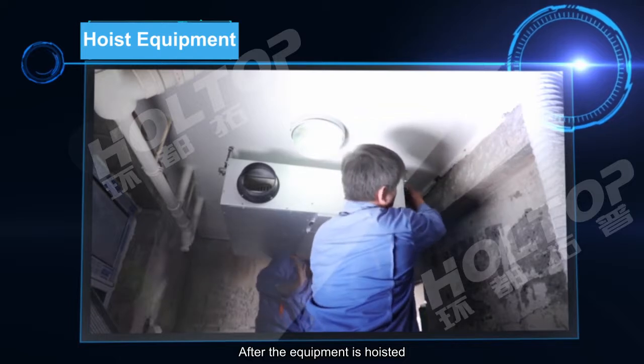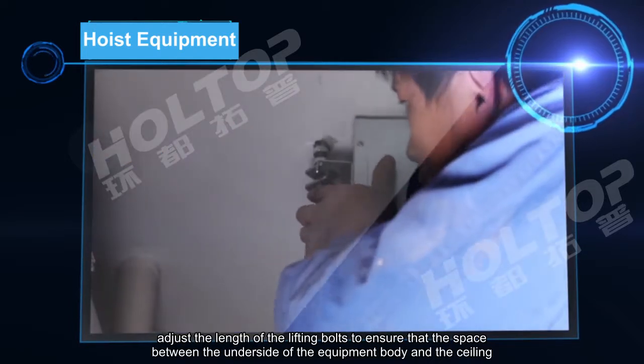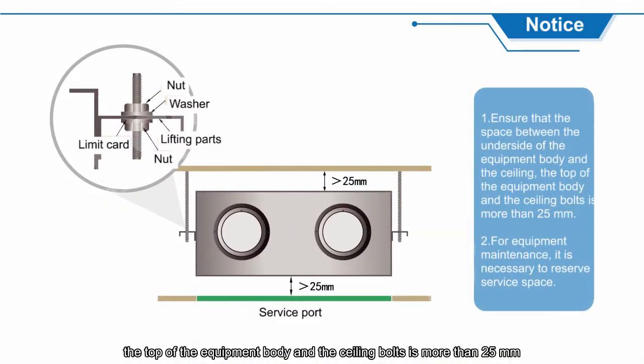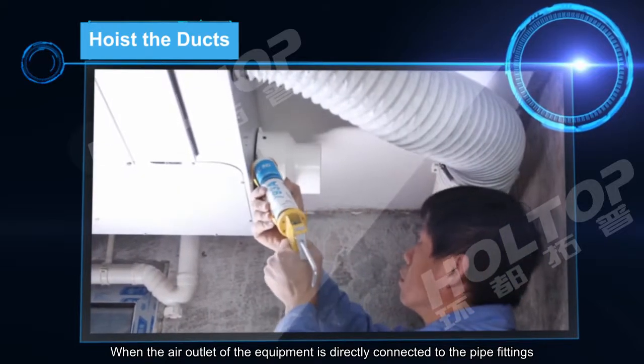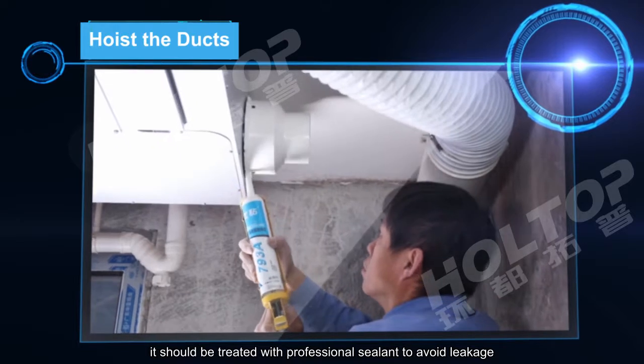After the equipment is hoisted, adjust the length of the lifting bolts to ensure that the space between the underside of the equipment body and the ceiling, and between the top of the equipment body and the ceiling bolts, is more than 25 mm. Also, ensure the equipment body is level. When the air outlet of the equipment is directly connected to pipe fittings, it should be treated with professional sealant to avoid leakage.